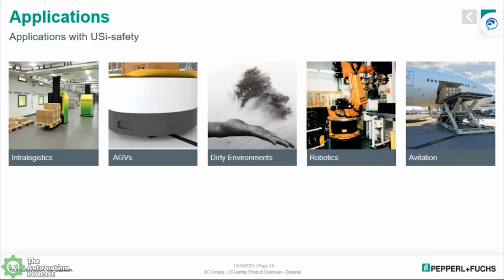So it's a great device for that, but it doesn't set a hard edge like the light curtain, right? Because it is sound based, you can set it for a meter and a half or 2 meters, but it may be within a centimeter or so as far as that fixed edge actually being. So it's better in those types of environments to use a light curtain or hard guarding for a fixed edge where you have to use a fixed edge, and do your safety distance calculations and those types of things. But in these applications we're looking at on the screen, the light curtains just would not work.